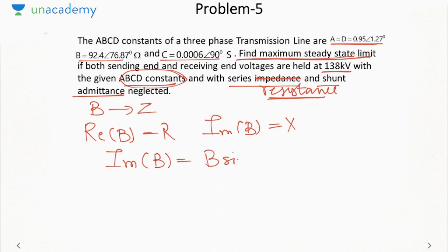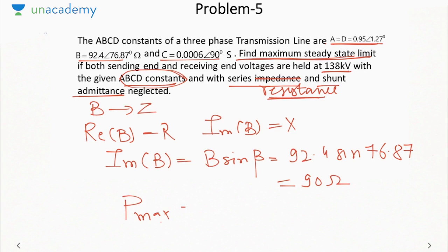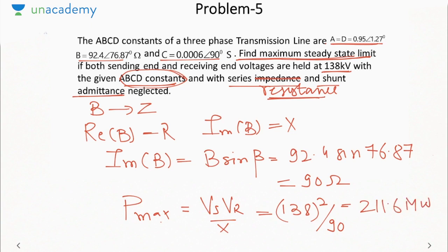So the imaginary part of B will be B sine beta, which is 92.4 sine 76.87. This comes out to be 90 ohms. Now this is a case of a short line with only reactance. So P max is Vs VR by X, that is 138 square by 90. This comes out to be 211.6 megawatt. You must always remember that B represents impedance and C represents admittance.